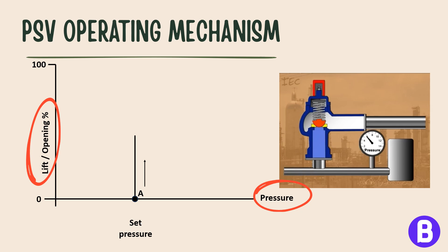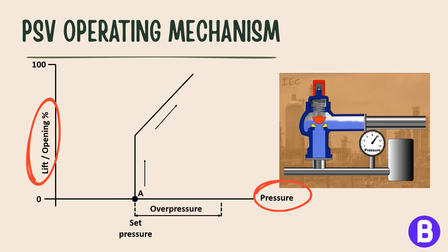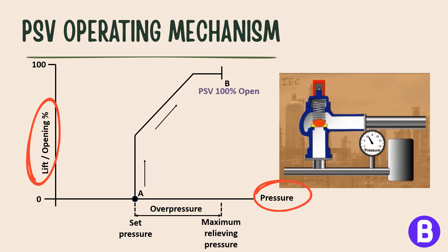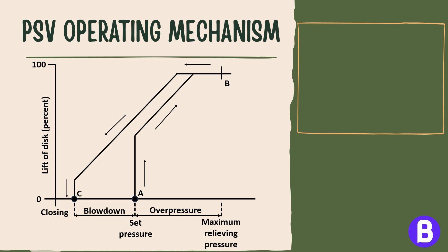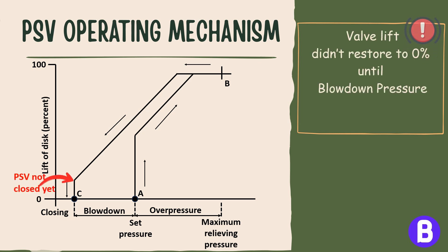As there is still not enough valve lift at the set pressure, the pressure continues to rise to the accumulation pressure and overpressure, and the valve will fully open to relieve the excess pressure. Finally, once the pressure is relieved, the valve moves to the blowdown phase where it reseats, preventing further release of fluid. Note that the valve lift did not restore to 0% until the blowdown pressure is reached, not at the set pressure.